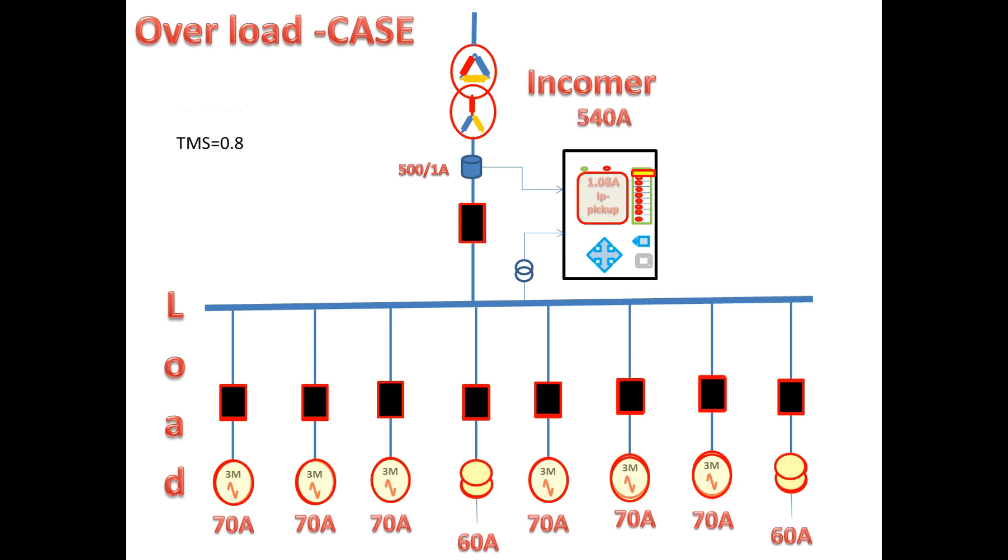Now we go for case 2. Here all the feeders are in overload so the overload current is very high. The actual current is 1.08 Amps. When you substitute in the formula, now the tripping time we get is only 12.55 seconds. Now the incomer will wait for only 12.55 seconds since the load current increased. After that it will give the tripping command to the incomer breaker.